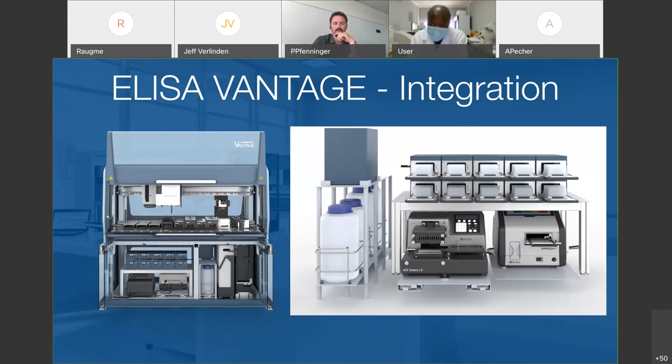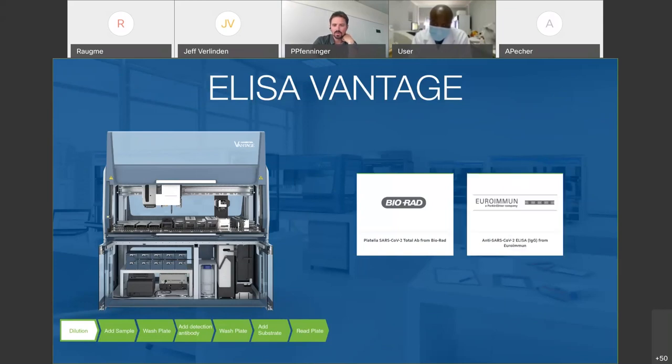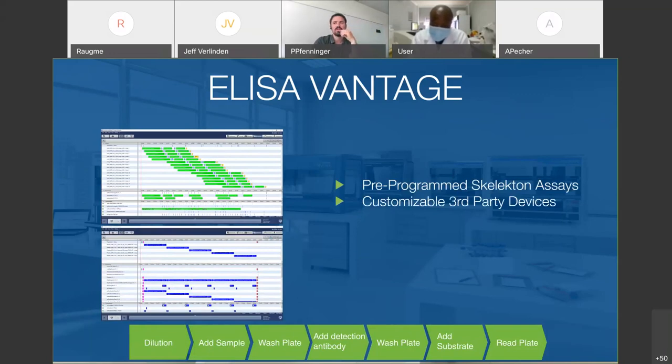Currently, we have pre-programmed assay data for Bio-Rad and Euroimmun. These are delivered as a skeleton run, so you have a template to start from. Your local application specialist would get this programming data from us and then adapt it to your needs on-site — in terms of throughput, labware, and location of third-party devices. Should you already have a different photometer on-site, you can use that one too. These are not fixed configurations where one part number equals one exact configuration; these are really suggestions for configurations to perform these ELISA assays.